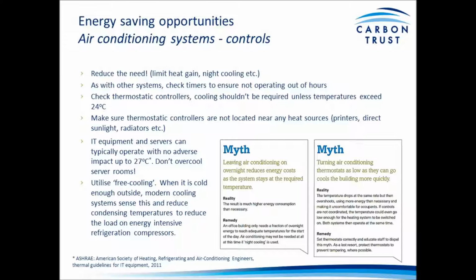And AC, again, we're going to start with controls because this is, again, the easiest and most cost-effective way to reduce energy consumption. As with other systems, check timers, make sure they're not running outside of operating hours. Check your thermostatic controls. Cooling shouldn't really be required in offices unless temperatures exceed 24 degrees Celsius. You can negotiate that with your office staff, but that is our guidance. And make sure thermostatic controllers are not located near any heat sources, printers, direct sunlight, radiators, etc.